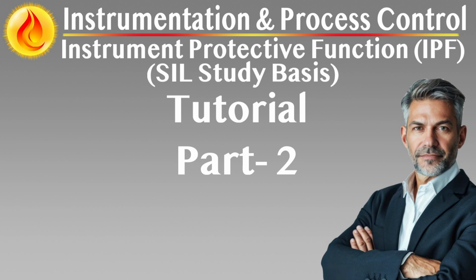Application in IPF design and SIL validation. Understanding the PST allows engineers to select appropriate detection technology. For short PST scenarios, fast response transmitters, e.g. for vapor pressure or flow surge, are essential. Evaluate actuator speed and valve stroke times. Final elements must fully close or open within the PST window, including any fail-safe or pressure venting delays.